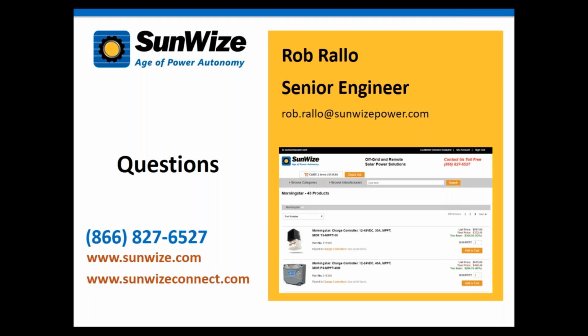I'd like to also just reiterate that you need to be careful. You should never install batteries in a sealed enclosure, which NEMA 4 and 4X are. So those people that do it should be using some type of breather vent to allow any buildup of gas to get out. So you should always have a vented enclosure of some form for the batteries, and hence the reason our enclosures are NEMA 3R, that allows that.